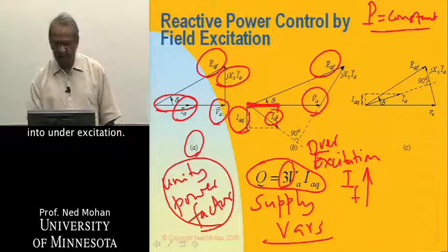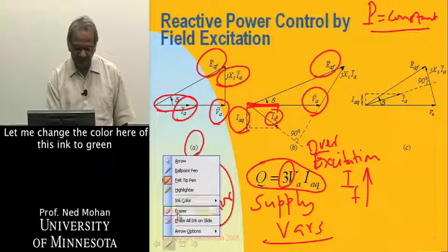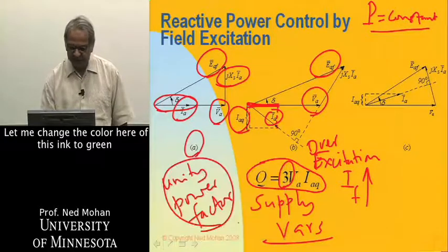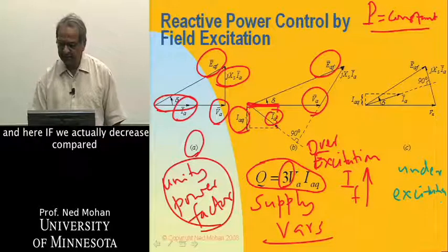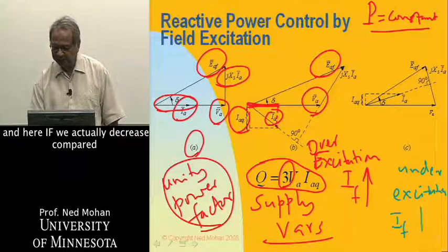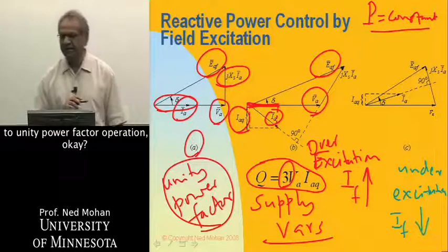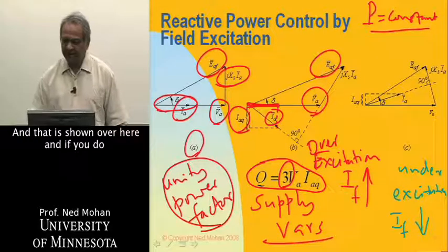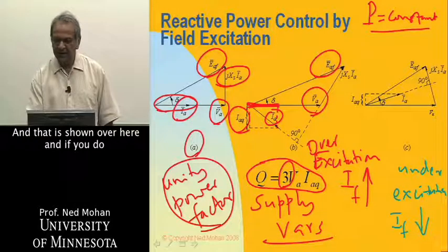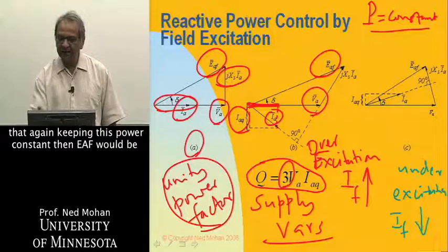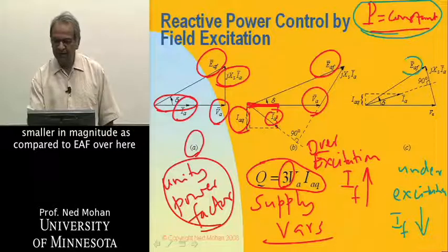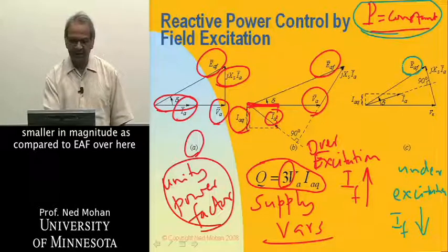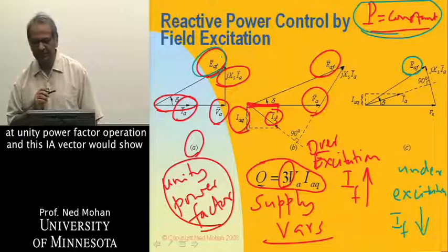In the same manner, we can go into under-excitation — shown here in green. Here IF is actually decreased compared to unity power factor operation. Keeping power constant, EAF would be smaller in magnitude compared to unity power factor operation.